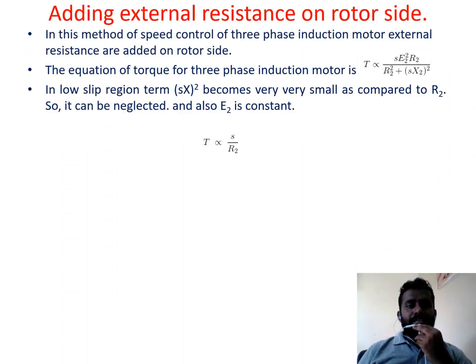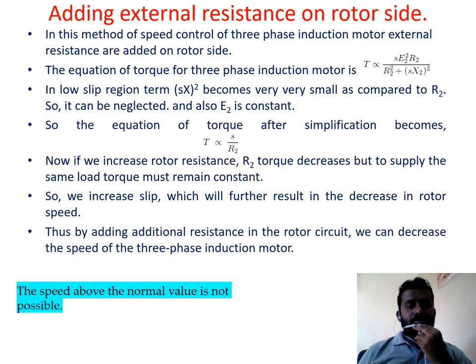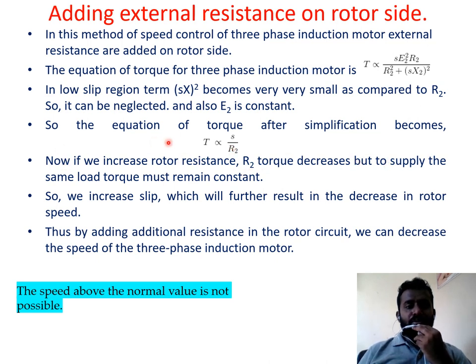Adding external resistance on the rotor side: external resistance can be added on the rotor side. In the low slip region, S²X2² is very small compared to R2 and can be neglected. With E2 constant, T is proportional to S/R2. If rotor resistance R2 increases, torque decreases. To supply the same load torque, slip must increase, which decreases rotor speed. Thus, by adding resistance in the rotor circuit, speed can be controlled below the normal speed only.